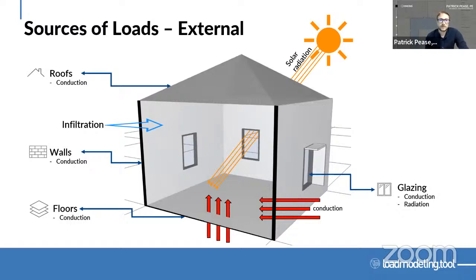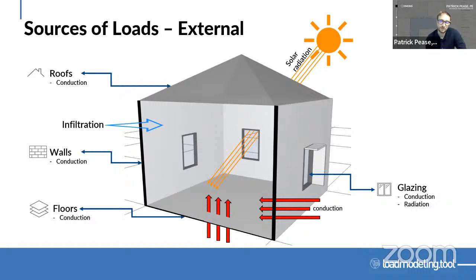Looking at the sources of loads externally — conduction is going to be one of the major ones. All the surfaces of our building will have some form of conduction, which is simply the transfer of heat through a surface adjacent to two different temperatures. Heat always travels from higher to lower: in winter when it's colder outside, heat leaves the building; in summer when it's hotter outside, heat enters through conduction. Solar radiation comes in through our windows and adds heat to the building based on window size and performance — the solar heat gain coefficient determines how much solar radiation can be blocked by the glass, and shade devices like fins can block some of that solar radiation as well.